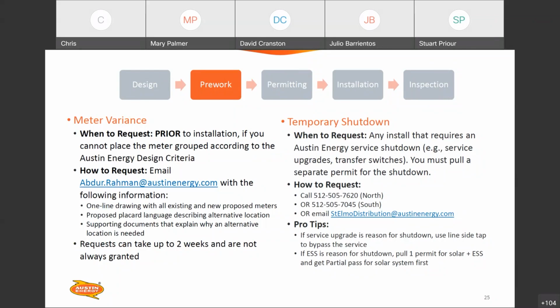If the energy storage system is the reason for the shutdown, you'll pull one permit, both the solar and the energy storage. And if you don't have the batteries and you'd like to commission the solar system while you're waiting on the batteries, it is acceptable for you to request inspection, and then, assuming the solar passes, we'll give you a partial pass, and there will be a second inspection on that same permit to inspect the batteries. All right, next slide.